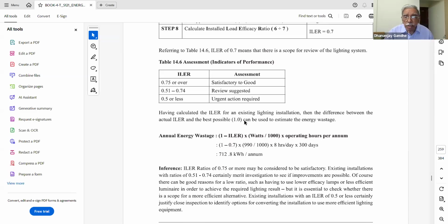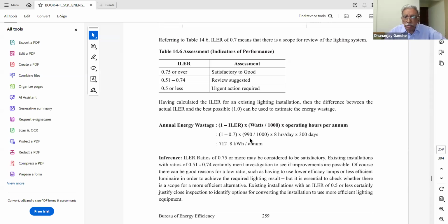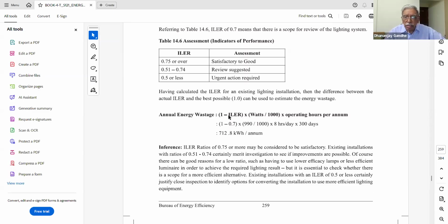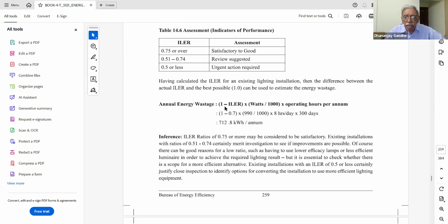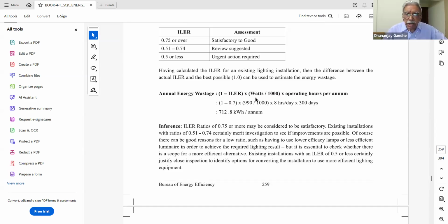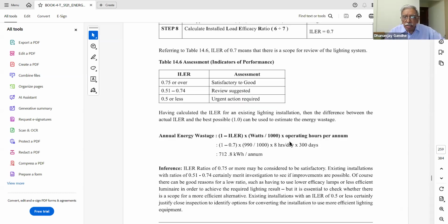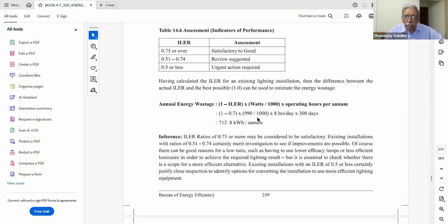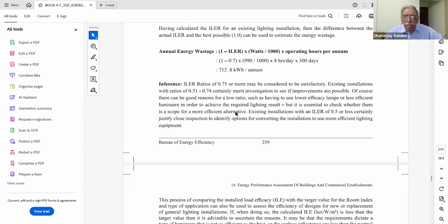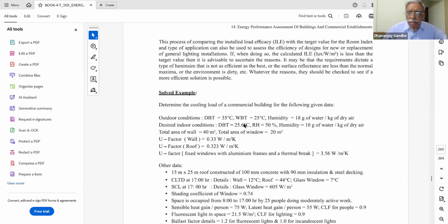Because the actual illumination is lower than the targeted illumination, it means that there is some loss, because you are not getting the illumination as per the target, which means there is energy wastage. It can be calculated by the formula: 1 minus ILER, multiplied by the connected watts, into operating hours, converted to kilowatts. So 1 minus ILER at that place is 0.7, so 0.3 multiplied by 990, the actual wattage of the lamps, divided by 1000 to get kilowatts, for 8 hours per day, 300 days. So the actual loss of energy is 712 kWh. That is worked out over here.